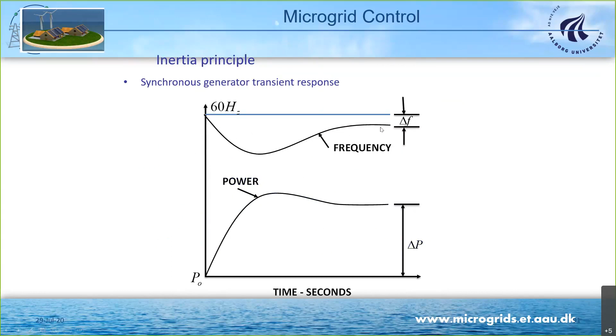You can see here what happened when we increase the power demand from the synchronous generator: automatically the frequency goes down. So dynamically the frequency goes down, and then you still have a steady state frequency error.